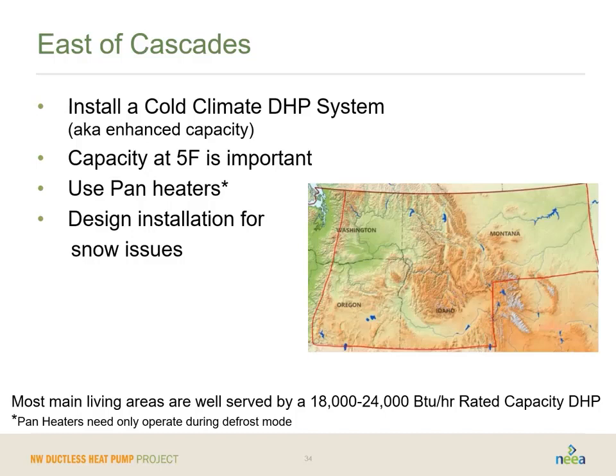So to wrap that up, west of the Cascades, a 1 to 1.5 ton system with a good turn down ratio is appropriate for most places unless you're at a high elevation or have a ton of windows. For east of the Cascades, in most scenarios, a cold climate ductless heat pump that is 1.5 to 2 tons will probably suffice for a lot of your displacement scenarios.